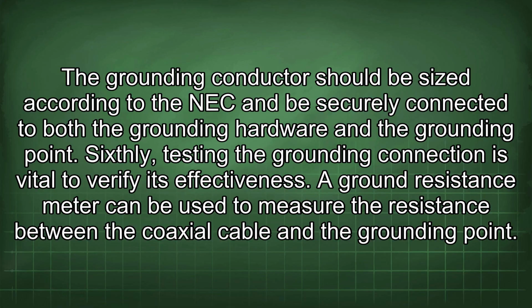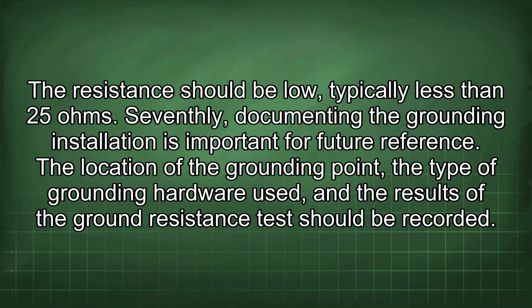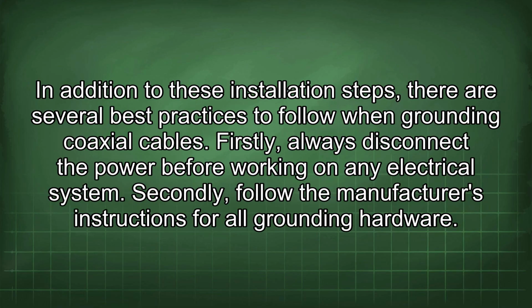A ground resistance meter can be used to measure the resistance between the coaxial cable and the grounding point. The resistance should be low, typically less than 25 ohms. Seventhly, documenting the grounding installation is important for future reference. The location of the grounding point, the type of grounding hardware used, and the results of the ground resistance test should be recorded. In addition to these installation steps, there are several best practices to follow when grounding coaxial cables.